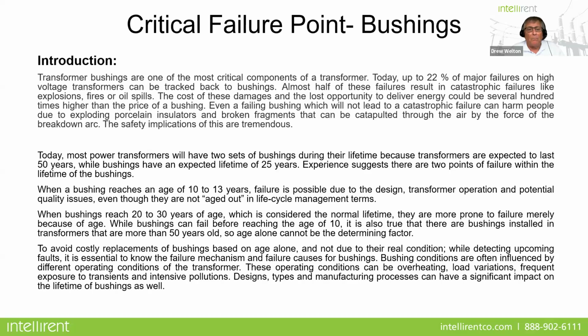So while bushings can fail before reaching the age of 10 years, it's also true that they are installed in transformers that are more than 50 years old. So if you're just using age as a determining factor for when to replace bushings, you could get yourself into big trouble. And of course, we want to avoid costly replacement of bushings based on age alone, not due to their real condition. So while detecting upcoming faults, it's essential to know the failure mechanism and failure causes behind the bushings.